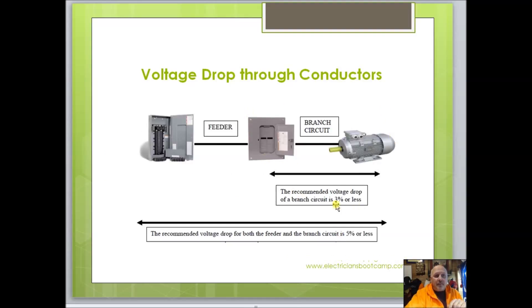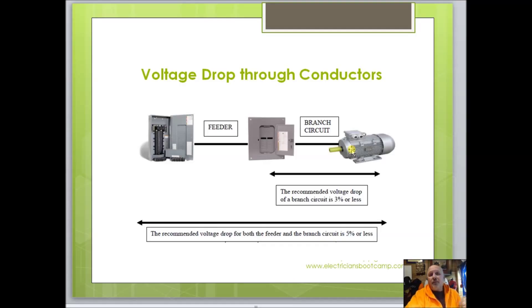Just to reiterate: three percent. If you didn't have a sub-panel, you'd be going from your main panel to your motor — still three percent. The five percent applies from a panel to the furthest device or motor away from your panel.